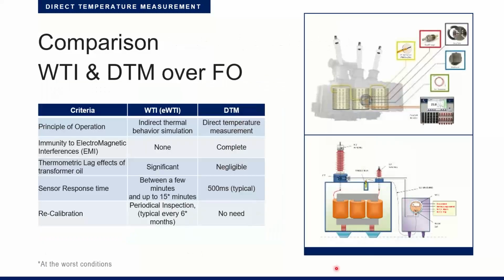You see both methods. The pictures on top show the direct temperature monitoring, and on the bottom you have the winding temperature indicator. So what's the principle of operation? For the winding temperature indicator, it's an indirect thermal behavior simulation. You have just a sensor measuring the oil temperature, and you're measuring the load of the transformer. If the load goes up and the temperature goes up, this runs through an algorithm, and it tells you what the temperature of the winding might be.